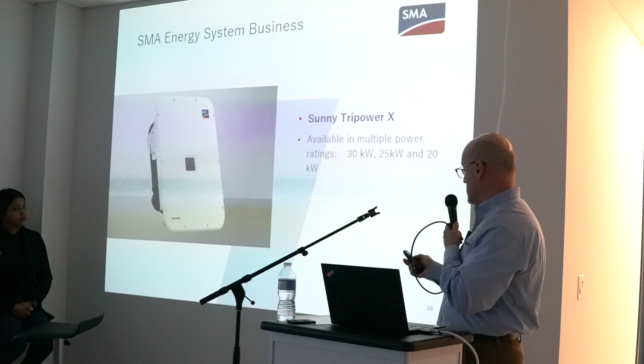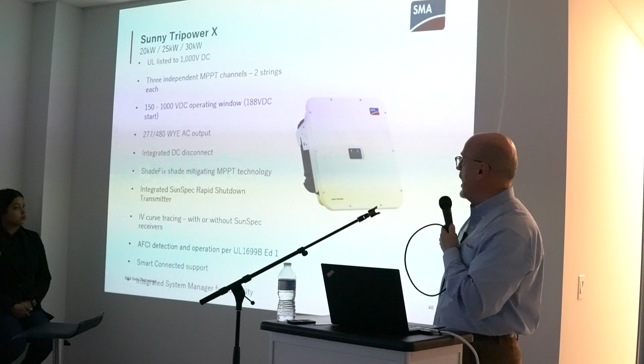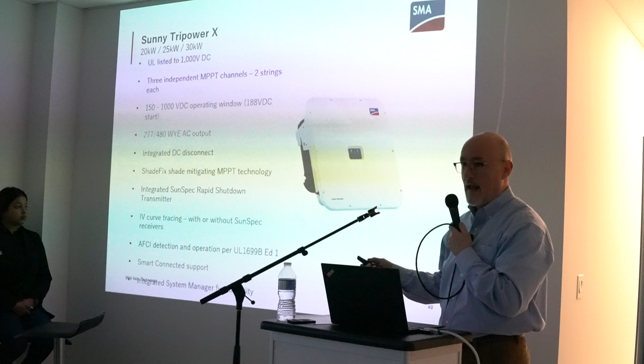Different form factor, as I mentioned. It's 1,000-volt DC, three independent MPPTs, or instances of ShadeFix, 2 strings per MPPT, so you avoid the fusing issue. So 6 strings. The operating window is the same as the CORE1. The start voltage is the same. Likewise, the AC is the same. It's 277/480Y. It does have an integrated DC disconnect. It does not have an integrated AC disconnect, just FYI.